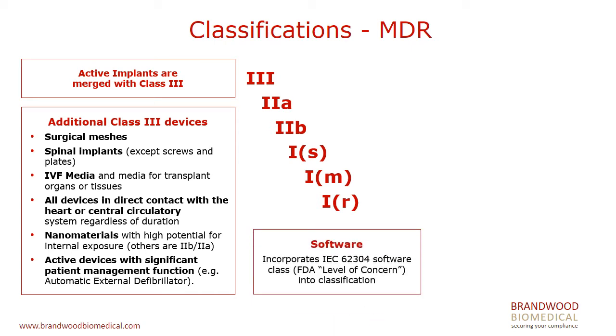Software has an interesting change in its classification here. Many of you will be familiar with the software risk classifications in the IEC 62304 standard and also in the United States FDA software guidance. There we have classification into, in FDA parlance, low, intermediate, and major levels of concern, and class A, B, C in the IEC standard. The idea is that as the software risk goes up, greater levels of validation are required. The new European classification for medical devices elegantly integrates those risk classes into the device classification, classifying software at elevating risk according to its level of concern or its software risk class in the standard.